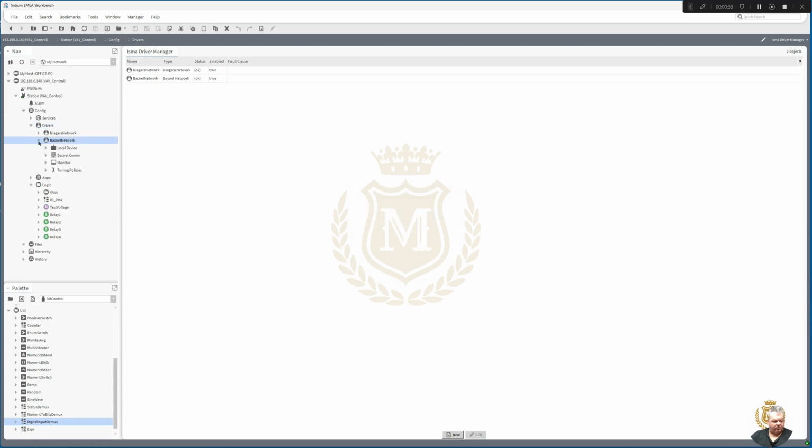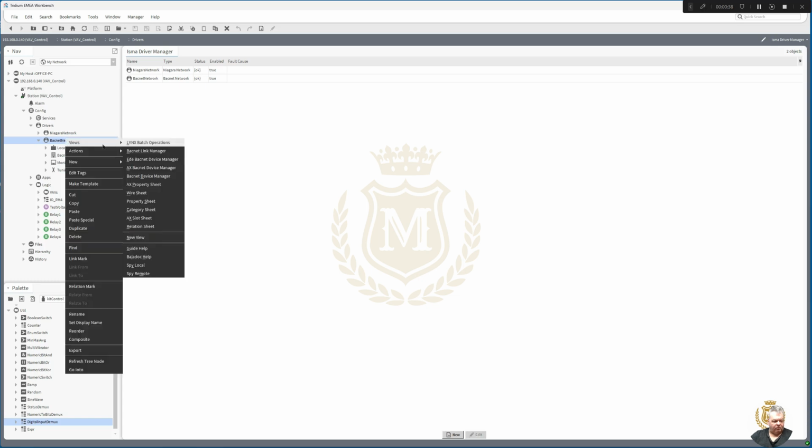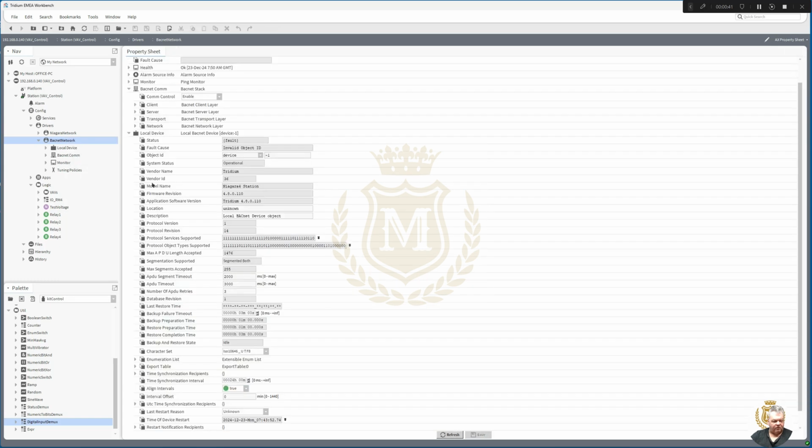We've got to do some configuration inside there. So I'm going to go Views and AX Property Sheet. I'm going to give it a device ID for the network. See how it's got fault there? Invalid object ID. So 1, 2, 3, 4 we'll call it. And I'll say it's Office Controller. But wherever it is, you can put that in there for the location. So that's that done.